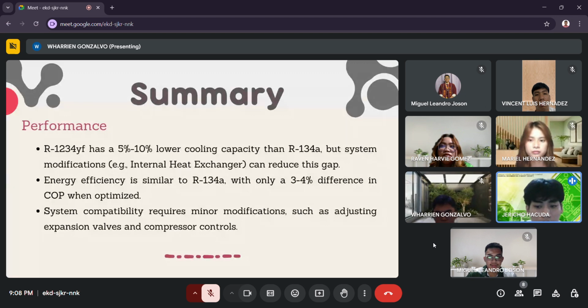For the summary, the performance of R1234yf has a 5% to 10% lower cooling capacity than R134a, but system modification can reduce this gap. Energy efficiency is similar to R134a, with only a 3 to 4% difference in COP when optimized. System compatibility requires minor modifications such as adjusting expansion valves and compressor controls.